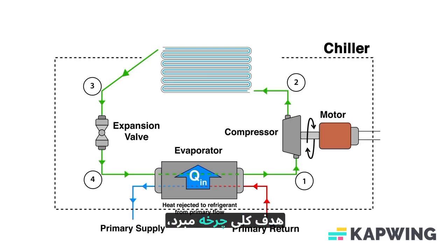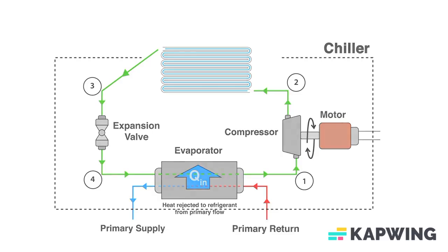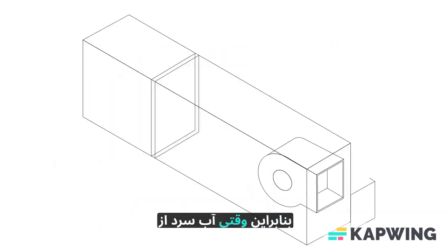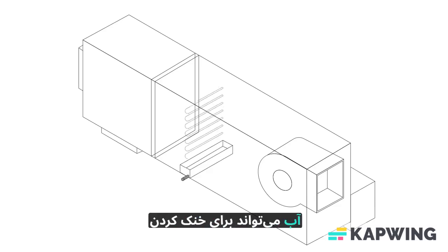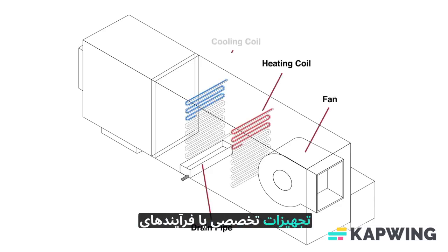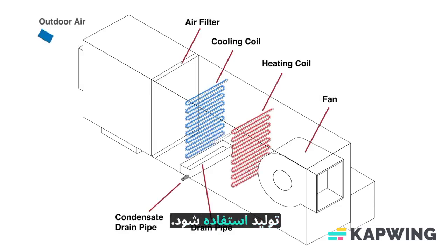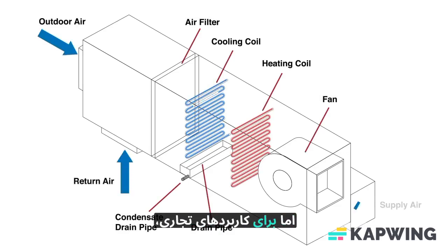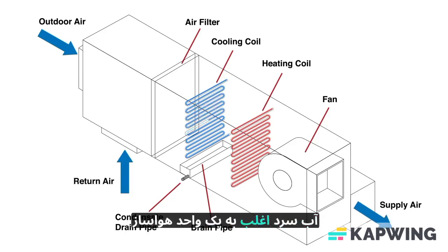The entire purpose of the refrigerant cycle is to collect heat from the chilled water and to somehow reject the heat outside. So, once the chilled water leaves the evaporator, where does it go? Well, that depends. In industrial applications, the water can be used to cool specialized equipment or manufacturing processes. But for commercial applications, the chilled water often goes to an air handler unit.